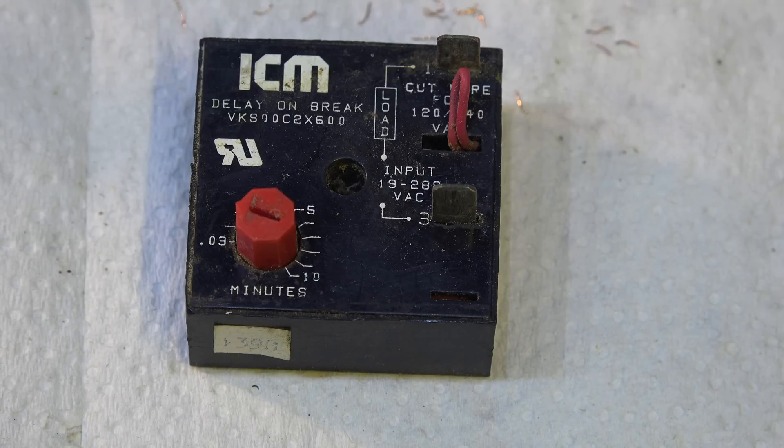So let's say you came out on a job, they were blowing fuses, nobody could figure out why. You might put one of these non-recycle timers on there and see if that kept them from blowing fuses.